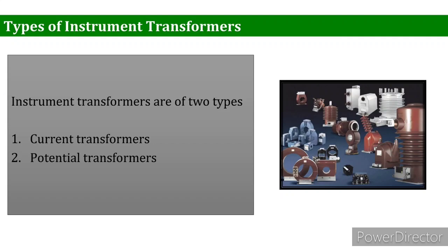Instrument transformers are basically categorized into two types: one is the current transformer (CT) and the other is the potential transformer (PT), also called the voltage transformer. Standard distribution or power transformers do not have CTs and PTs. CTs alone are used at commercial and industrial level where large amounts of electricity are consumed, and the current is stepped down so the meter can read it. For example, a turn ratio of 200:5 or 40:1 means if the real load is 40 amperes, it converts to 1 or 5 amperes.